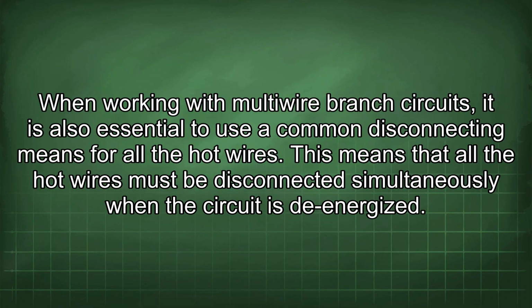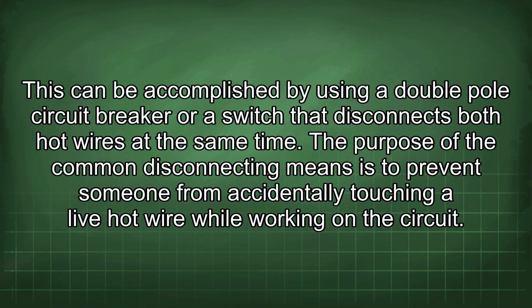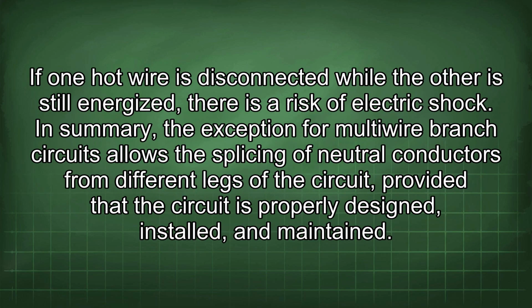When working with multi-wire branch circuits, it is also essential to use a common disconnecting means for all the hot wires. This means that all the hot wires must be disconnected simultaneously when the circuit is de-energized. This can be accomplished by using a double-pole circuit breaker or a switch that disconnects both hot wires at the same time. The purpose of the common disconnecting means is to prevent someone from accidentally touching a live hot wire while working on the circuit. If one hot wire is disconnected while the other is still energized, there is a risk of electric shock.